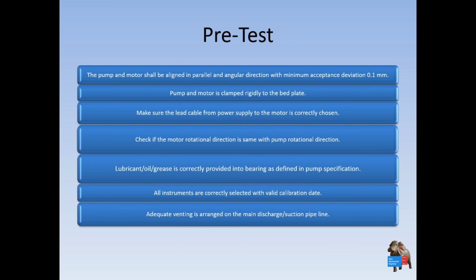Then you also need adequate venting arranged on the main discharge and suction of the pump, because the test rig is usually a circular closed loop. You don't want the suction to suck in air because the level of the water in the test rig, usually a tank or water reservoir, is lower than expected, which will make noise in the system. So you have to ensure that at the flow capacity, let's say 100 cubic meters per hour, there is no shortage of water during circulation.